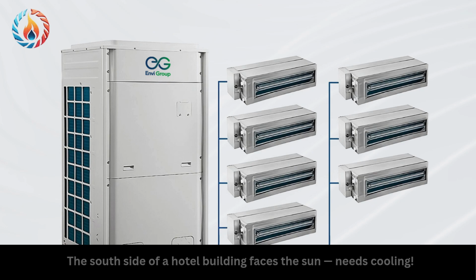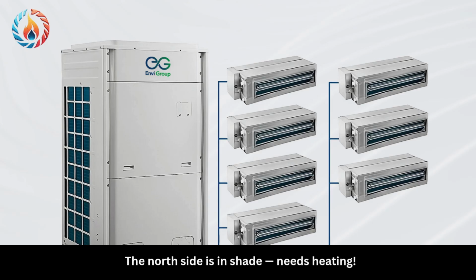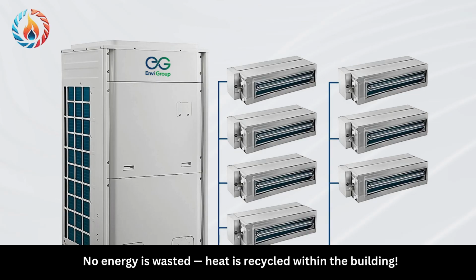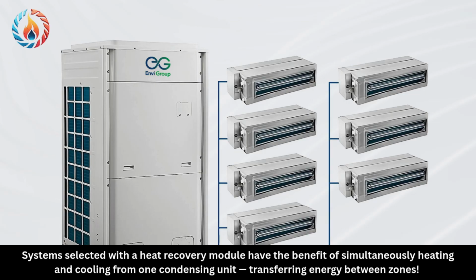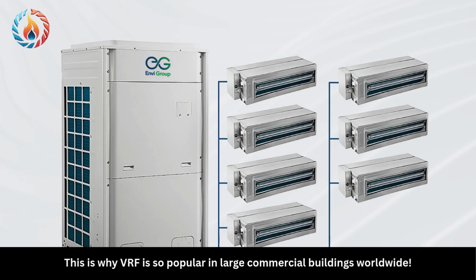Imagine this, guys. The south side of a hotel building faces the sun, needs cooling. The north side is in shade, needs heating. Heat recovery VRF handles both at the same time. It takes heat from the areas being cooled and transfers it to areas that need heating. This is incredibly energy efficient. No energy is wasted. Heat is recycled within the building. Systems selected with a heat recovery module have the benefit of simultaneously heating and cooling from one condensing unit, transferring energy between zones. This is why VRF is so popular in large commercial buildings worldwide.